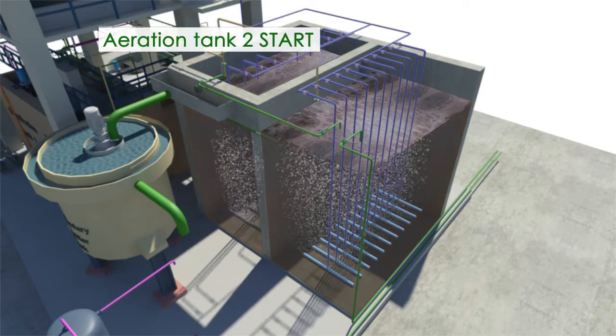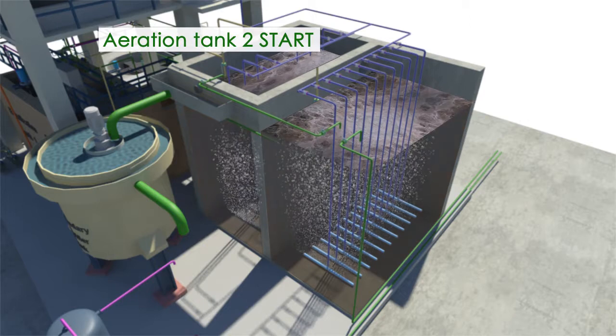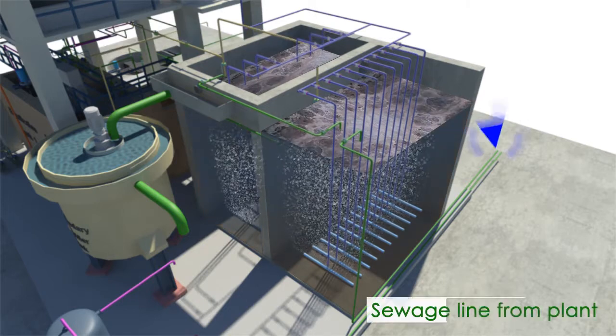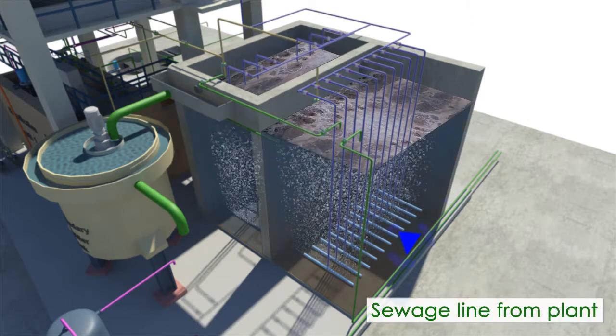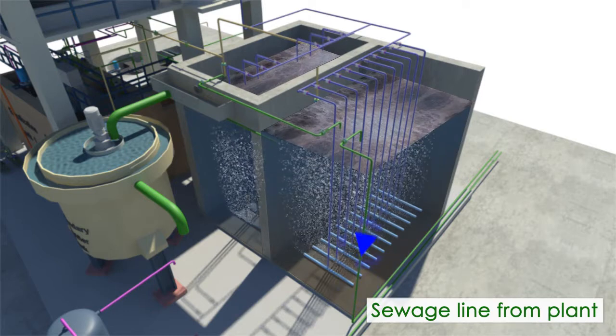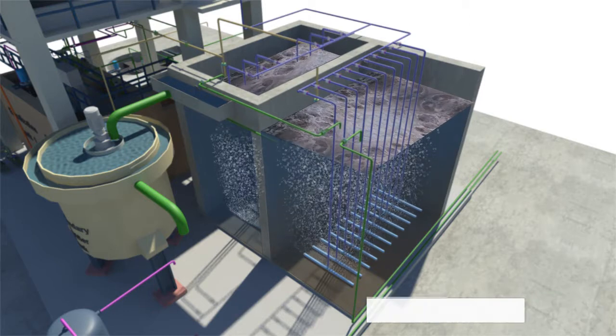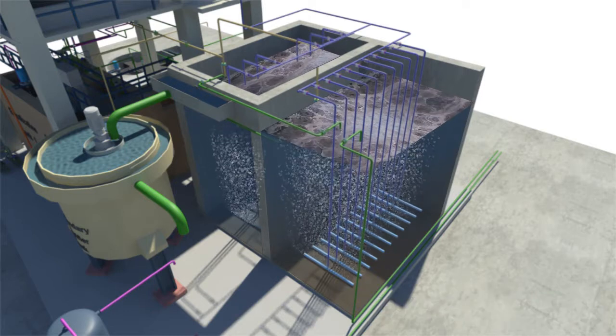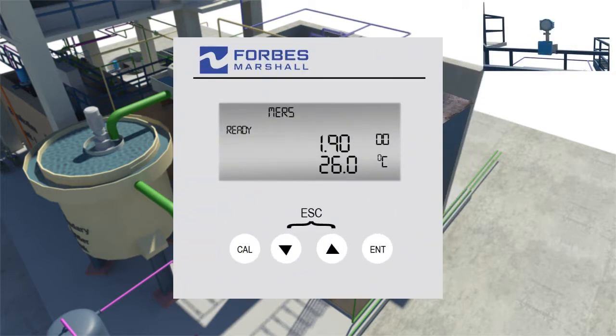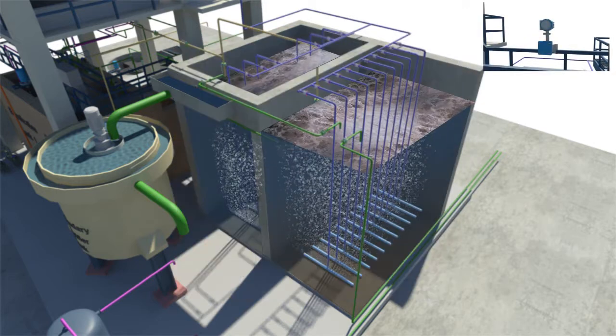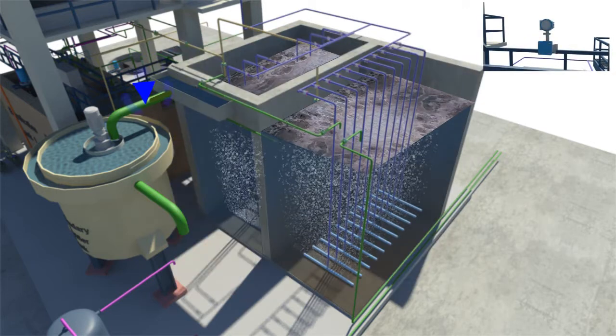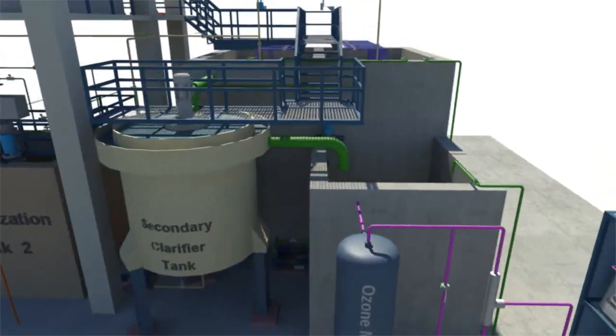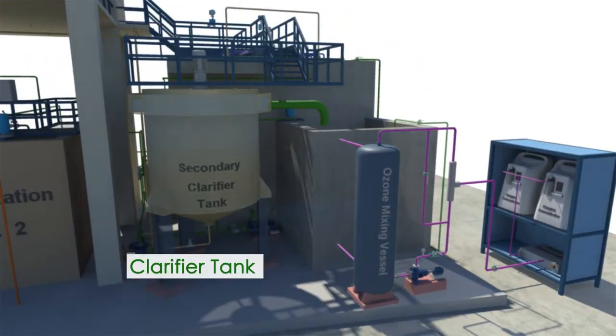The effluent then begins to flow into tank 2 and further to the secondary clarifier. The sludge recycle pump operates continuously in manual mode. A DO meter is provided to analyze the oxygen level in the aeration tank. The treated effluent from the secondary clarifier flows by gravity to the filter feed tank for further tertiary purification.